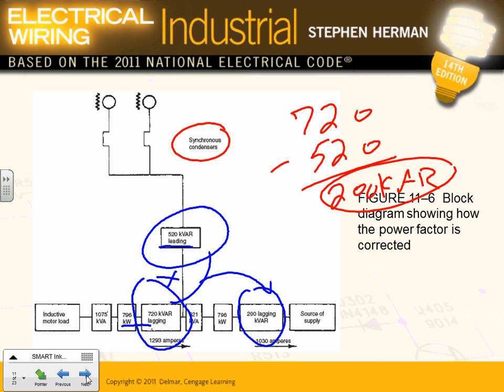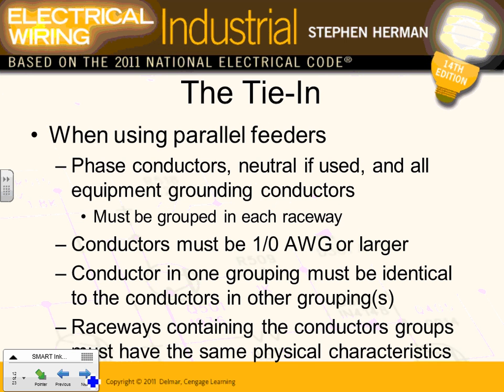So tomorrow, when I have an example for you, and I say I'm adding a condenser or capacitor, that's what it does. It knocks it down to this, to subtract it, basically. Okay? So if I want to have 100% power factor, what do you think this value should be to knock this down to 0? 720. Why didn't I do 720? Because if you correct to 100% power factor, what happened? When your motors are down, you overcorrect. So I'll go over this calculation also tomorrow.